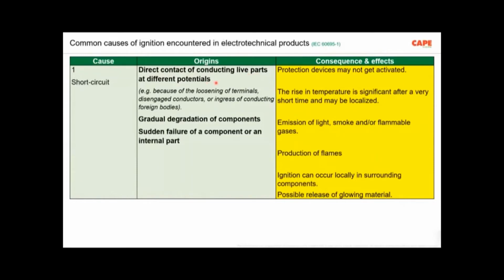So your conductors, your wires, are having different voltages, and due to an insulation degradation or insulation failure, if these two wires are in touch, of course, you get a short circuit. The second problem is gradual degradation of the components. That means the devices used in your equipment, such as capacitors or MOVs or diodes, if they degrade, or in a wound transformer or a small instrument transformer, if the winding insulation fails, of course, it can also create a short circuit. The third part is the sudden failure of a component in the internal part of an equipment. These three are the recognized origins of short circuit, and the consequences or the effect.